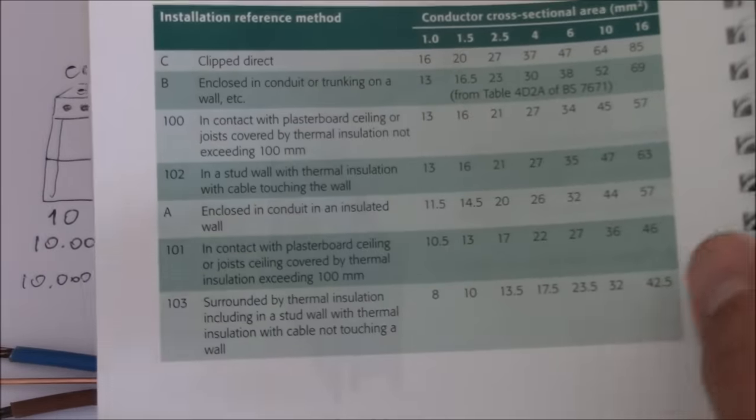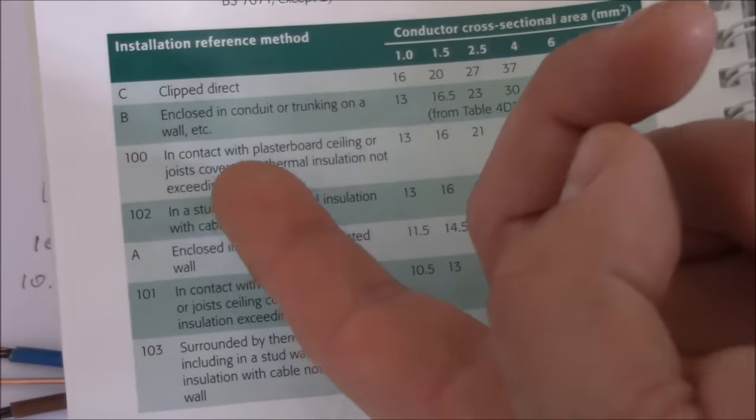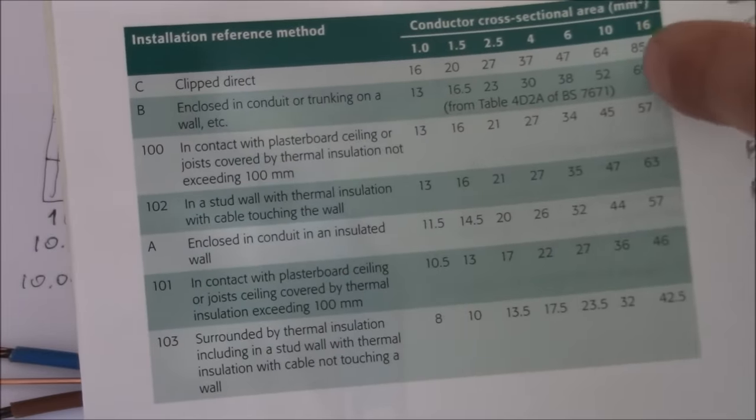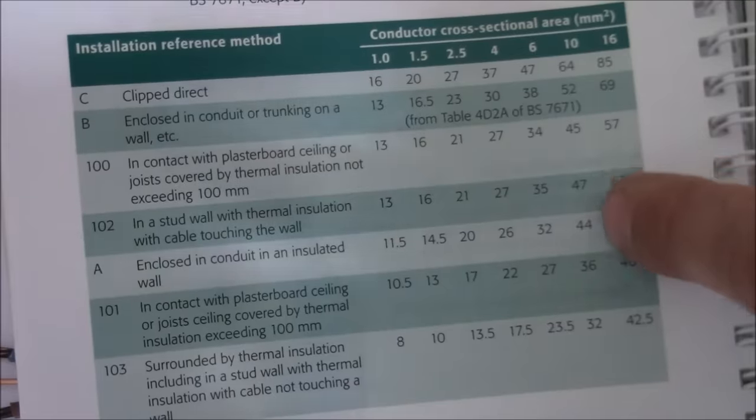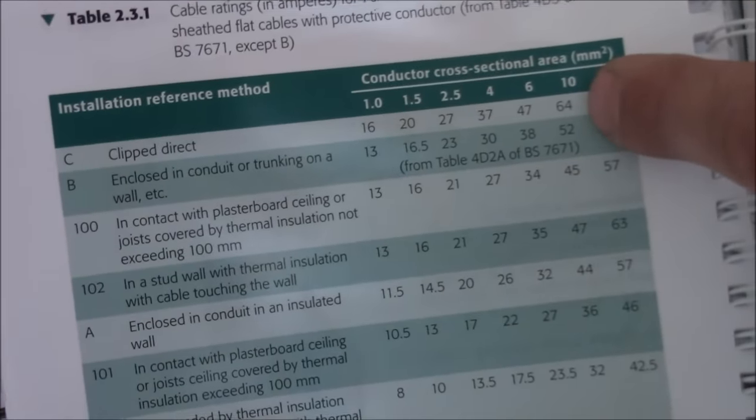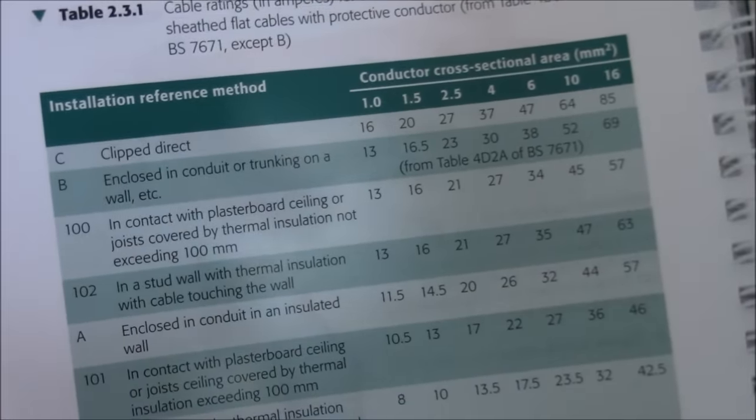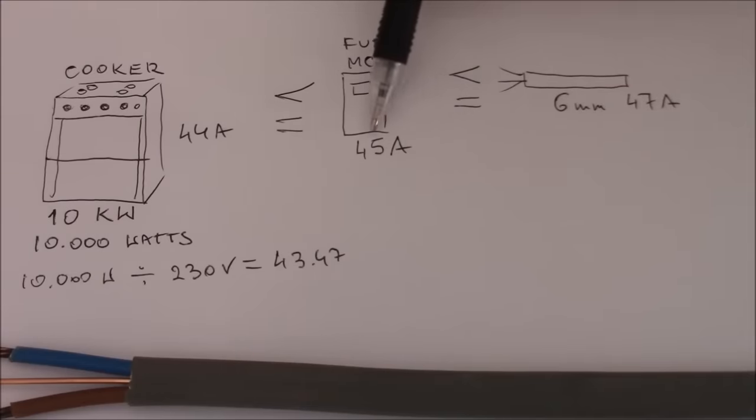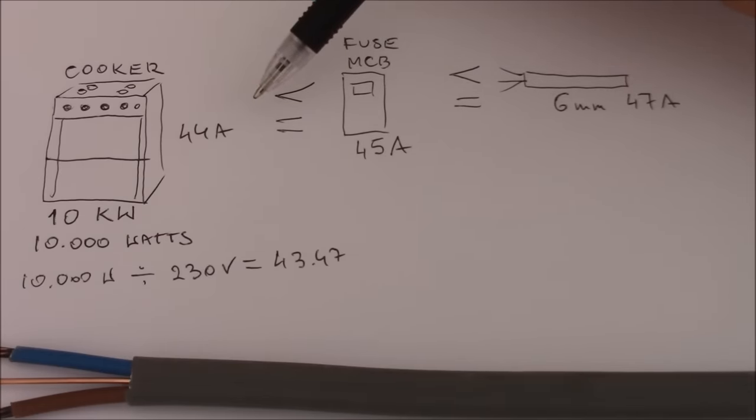So if you use the same cable and install it for example touching the insulation, then obviously the rating goes down quite a bit and then you have to use the 10 mm cable. So as you see these numbers are just minimum. It's very close to the 44 amp that our cooker draws. So basically I would suggest anyway to install a 10 mm cable as nobody at home installs it by clipping it to the wall. So basically 10 mm cable would be much much better.